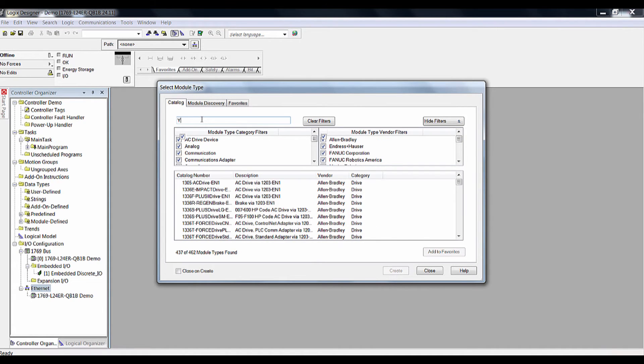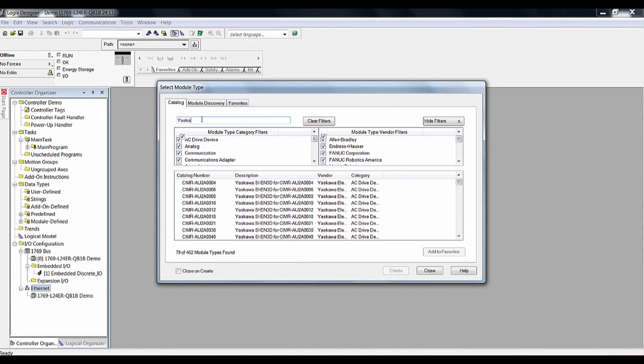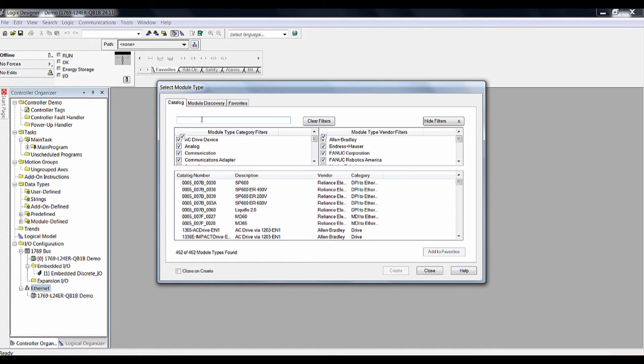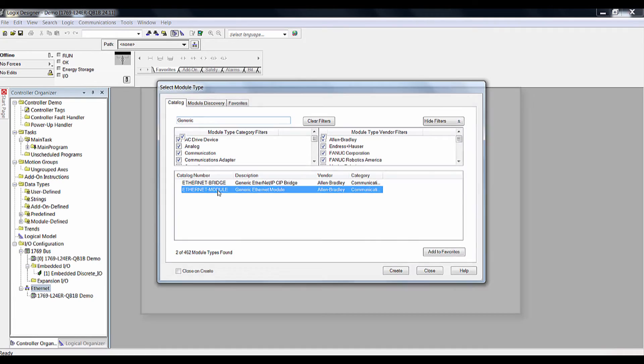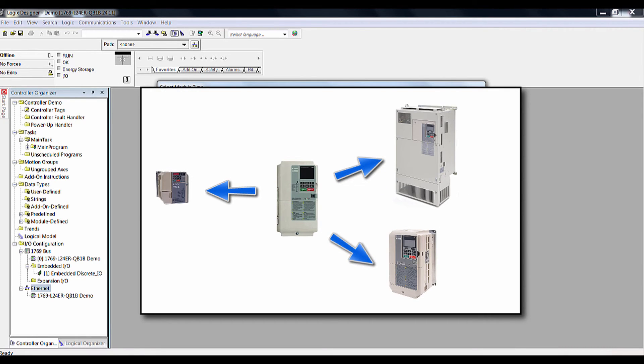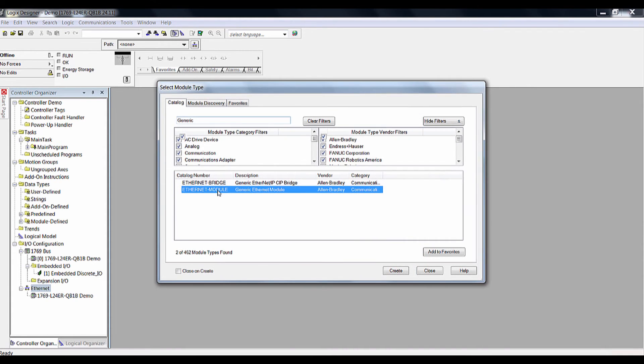If we wished, we could import the EDS files for our A1000 and then our A1000 would be included on the list of things to add to the PLC. Rather, we will add our VFD to the network as a generic Ethernet module. That way, if later we want to replace the VFD with a different size or different generation of drive, we will not have to change anything provided we use the same IP address and assemblies.